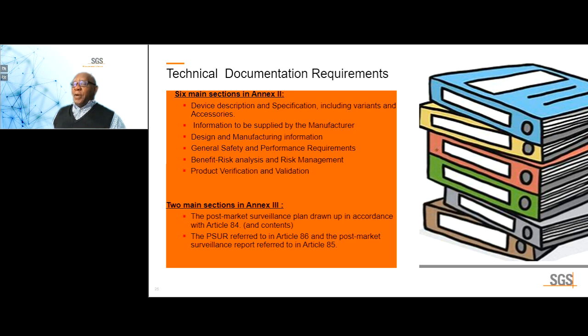And then in the post-market phase, the requirements are much more explicit under the MDR than they ever were under the MDD. And the 2 main sections are post-market surveillance plan drawn up in accordance with Article 84, and the periodic safety update reports referred to in Article 86, and the post-market surveillance report referred to in Article 85. I'll talk to the PMS requirements later on in this presentation.